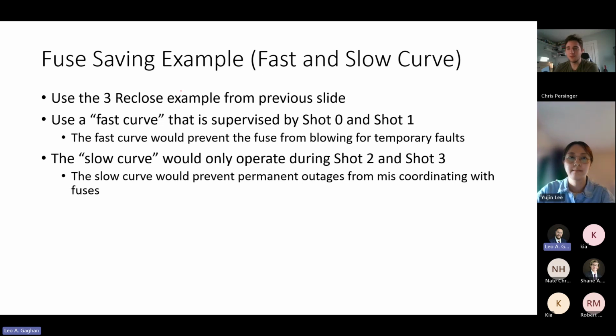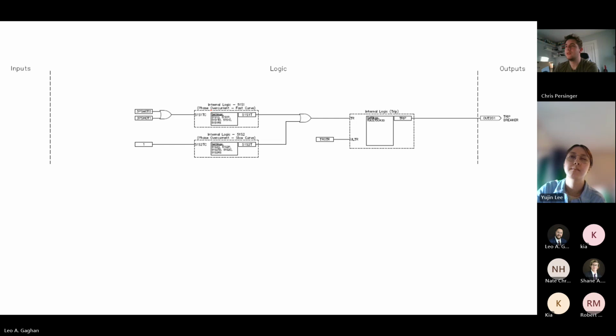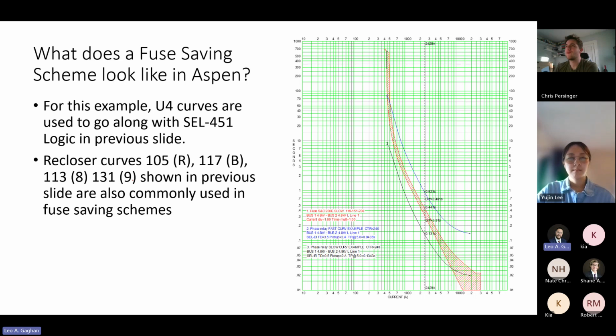Going back to some of our previous examples, we had the 3 reclose example from a previous slide. We can have a fast curve that is supervised by that shot 0 and shot 1 that we talked about. And then we could have a slow curve that would only operate during shots 2 and 3. So yeah, pretty easy logic for it, right? It just goes to those torque equations. So here's a pretty good example of that fuse saving scheme. This curve right here, we'll say operates on shots 0 and 1. This guy will operate on shots 2 and 3.